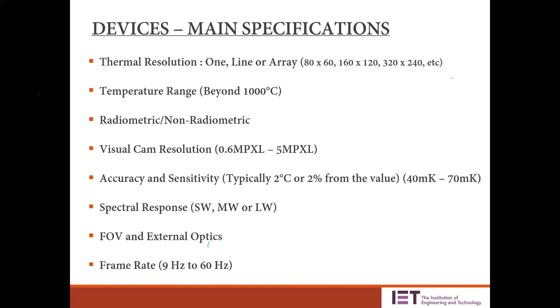Same with search and rescue. If you are trying to look for a boy who has got lost in the jungle, which we'll see in some photographs in the slides to come, you would definitely need a 50 or 60 Hertz frame rate in your device. Yeah, really important. If you have a device, carry the case with it. If that is a high-end device, you will have a hard case, use it. Don't carry the imager around without it.